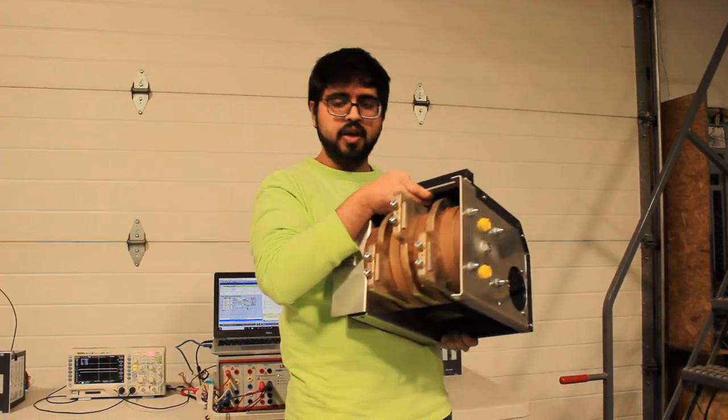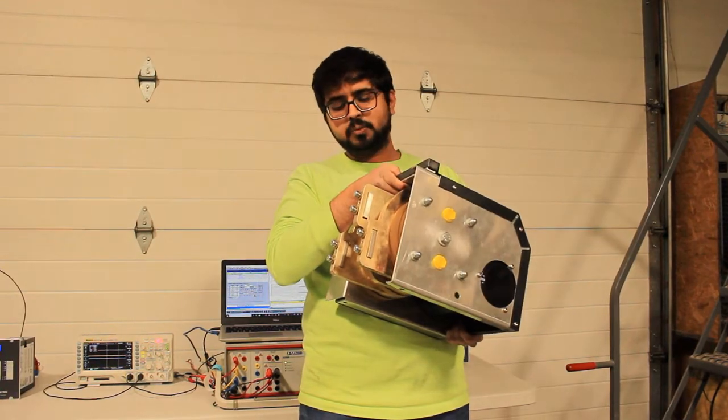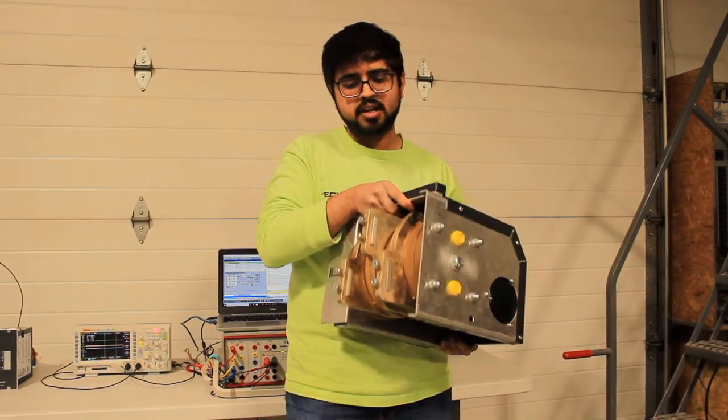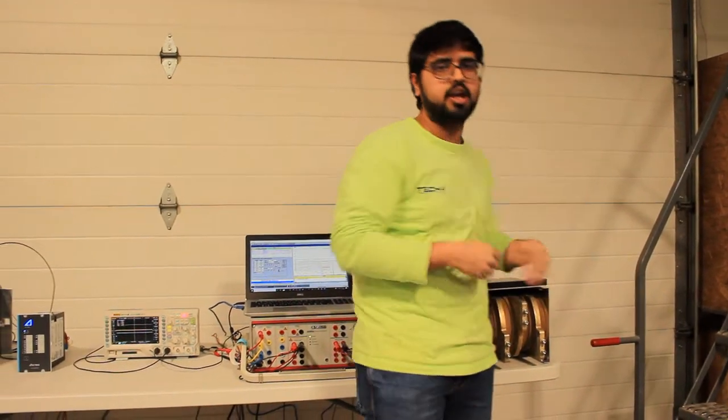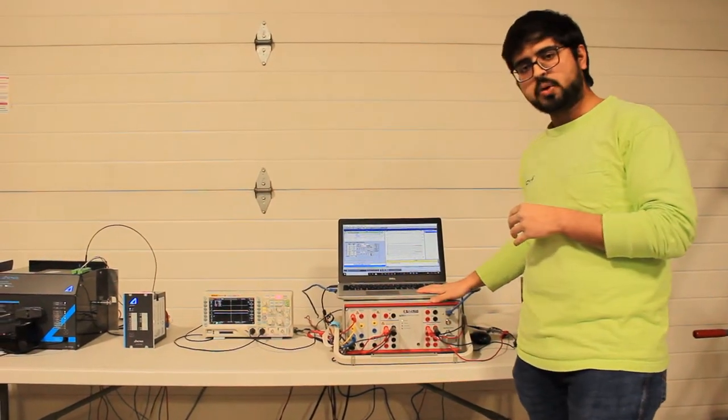Let me show you the back of the quencher. This is how it's mounted on the bus bars, the three phases. In this setup right here, to demonstrate an actual collapsing of the voltage, we have induced voltage on one of the phases. When the quencher trips we can see the voltage collapsing and measure the time on the oscilloscope.